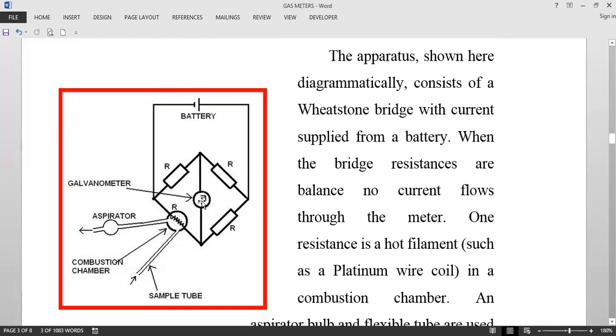Again, we have to remember not to use this in an inert condition, because we need oxygen for combustion to take place. Normally another equipment called a tank scope is used when carrying out gas freeing of a space, as it can measure gases at higher concentrations also. Once the amount of gas has gone below the lower explosive limit, you then use this explosimeter to see the concentration of gases inside the space.